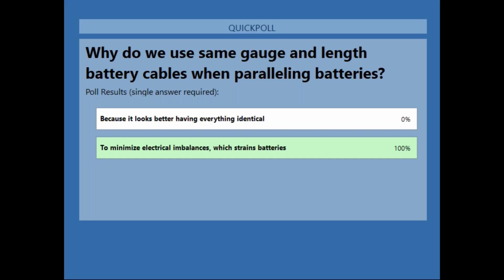The other issue is that all the connections are on the battery to the right, with none on the battery to the left. This is the other way he unbalanced it, since the batteries on the right are getting used more than the ones on the left. Interestingly, the voltages at the bottom show the left batteries at a higher voltage than the right ones because they're not being used or balanced the same way. If you moved that negative connection from battery 4 to battery 3, to the same negative post, it would balance that problem, and the voltages would end up a lot closer.